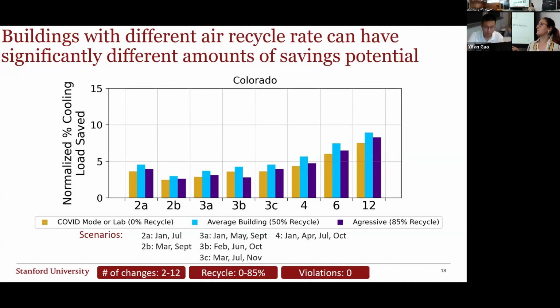However, interestingly and surprisingly, when you go up to 85% recycle in Colorado, the savings are actually less than at 50% recycle—higher than 0, but less than 50. That's because in Colorado, the outside air is usually between your indoor air temperature of 72 and your low point of 55 in the air conditioning. So at this location you have access to free cooling if you use more outside air, meaning reducing the recycle isn't ideal in this scenario.